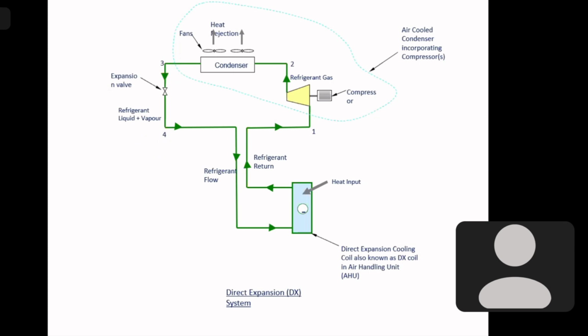So that expanded refrigerant is fed directly into the cooling coil, and we pass air over the cooling coil, which cools the return air from the room, and we supply that air back to the room. So as the refrigerant is directly expanded into the cooling coil, we call it a direct expansion system. There are other systems also, we'll come to that. Next slide.